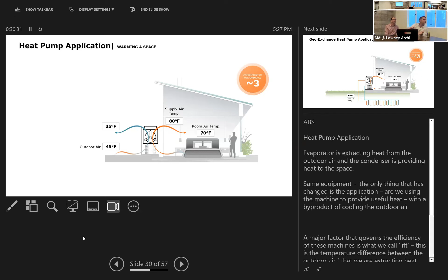A really key factor that determines the efficiencies of these machines is something called lift. And that's the temperature difference between the outdoor air here, which is at 45 F, and the temperature that you're trying to create on the other side, which in this case is 80 F. So in this case, this would have a lift of 35 degrees. Okay, and the smaller you can make that lift, the more efficient the machine operates.